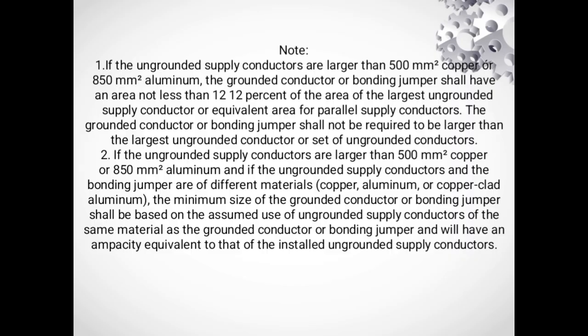The grounded conductor or bonding jumper shall not be required to be larger than the largest ungrounded conductor or set of ungrounded conductors. 2. If the ungrounded supply conductors are larger than 500 mm squared copper or 850 mm squared aluminum, and if the ungrounded supply conductors and the bonding jumpers are of different materials, copper, aluminum, or copper-clad aluminum, the minimum size of the grounded conductor or bonding jumper shall be based on the assumed use of ungrounded supply conductors of the same material as the grounded conductor or bonding jumper and will have an ampacity equivalent to that of the installed ungrounded supply conductors.